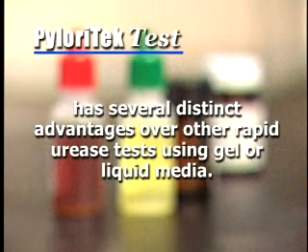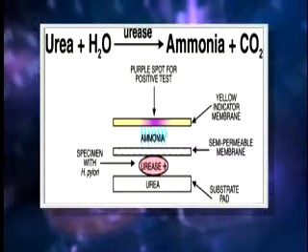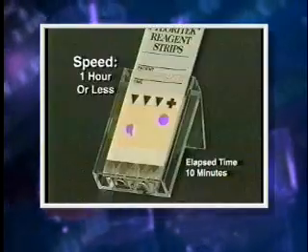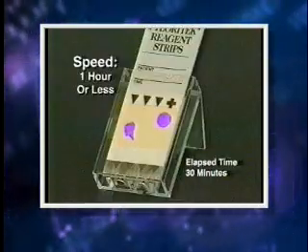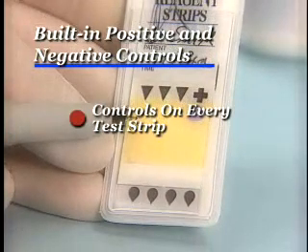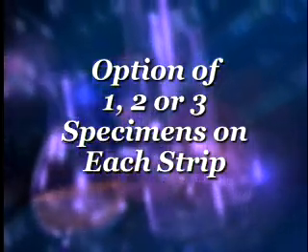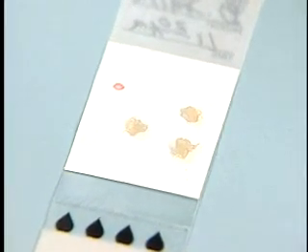PyloriTek has several distinct advantages over other rapid urease tests using gel or liquid media. The patented PyloriTek method allows the urea, urease, and ammonia detection reaction to take place in separate optimal environments. The final result is available in one hour, allowing discussion of results with the patient before they leave the clinic, with most positives appearing in 20 minutes or less. The reactive positive control and negative control are both present on every test and run automatically without extra steps or reagents. Up to three specimens from the same patient can be placed on a single PyloriTek strip, with separate, distinct results for each biopsy.